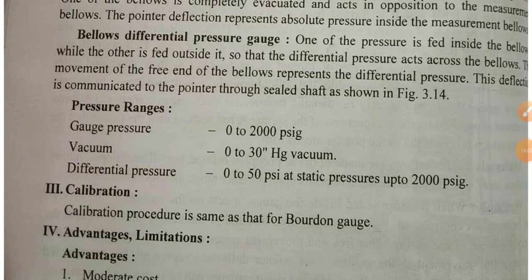One of the pressures is fed inside the bellows while the other is fed outside, so that the differential pressure acts across the bellows. The movement of the free end of the bellows represents the differential pressure. Write down the pressure ranges: the ranges of gauge pressure, vacuum pressure and differential pressure are given separately.